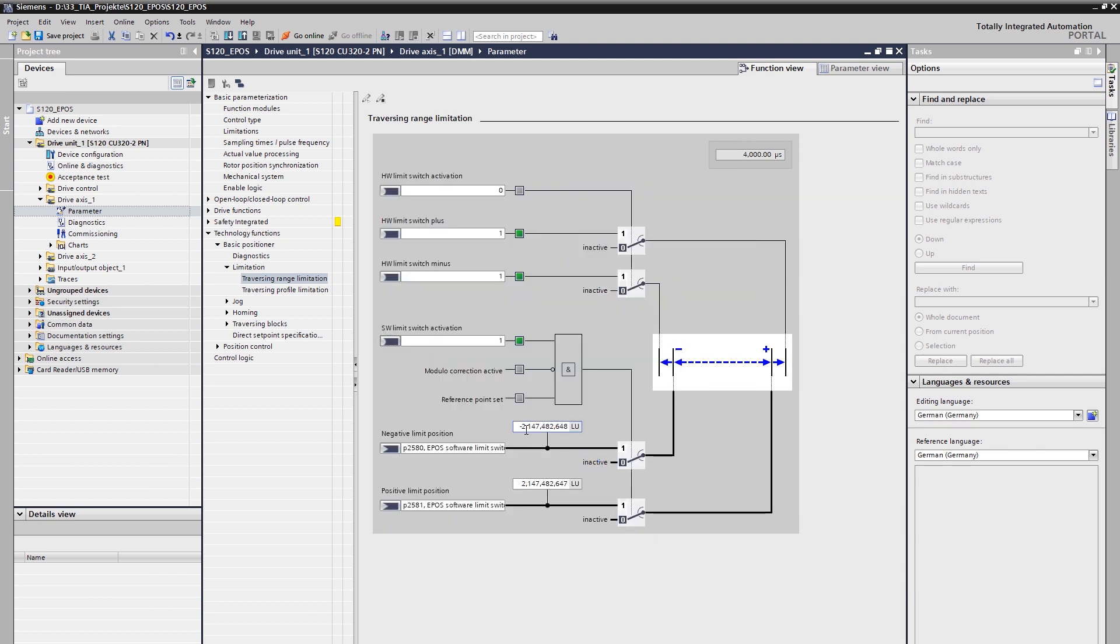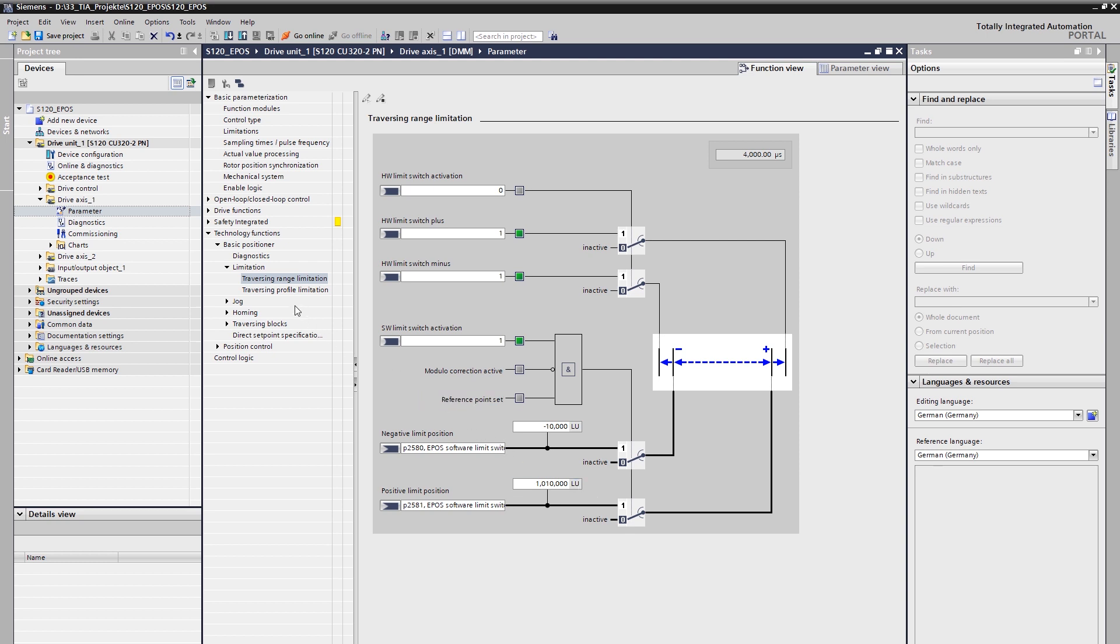For our example, we only use the software limit switches. With active software limit switches, the target position is checked. If this is outside the travel range, a warning is issued. The travel range or the working range in our example application is 1 m or 1000 mm. The selected positioning resolution in micrometer results in a travel range between 0 LU and 1000000 LU. Experience has shown that the end positions are selected to be slightly larger than the required travel range for the application. In this example, 10 mm or 10000 LU is added in each case.